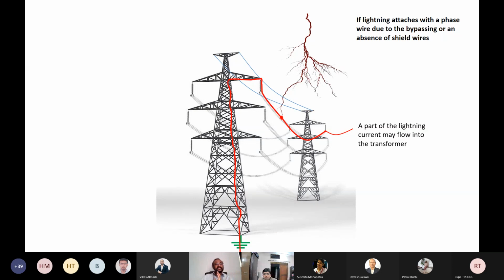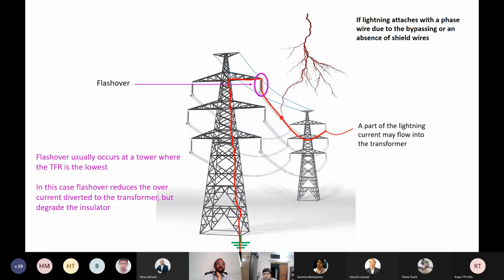Okay, now what is the scenario? Flashover usually occurs at a tower where the TFR is the lowest. Now don't forget that if there is a bypassing of the shielding wire and lightning gets attached to a live wire, the flashover across the insulator is most probable usually at a tower where the tower footing resistance is the lowest. So it is understood, isn't it? Because that is the best path for the lightning current to get into the earth. Now, in this case, flashover reduces the overcurrent diverted to the transformer. So if this flashover happens, now it is not back flashover, it is flashover, the transformer will be less affected, but on the other hand, the insulator will be degraded.